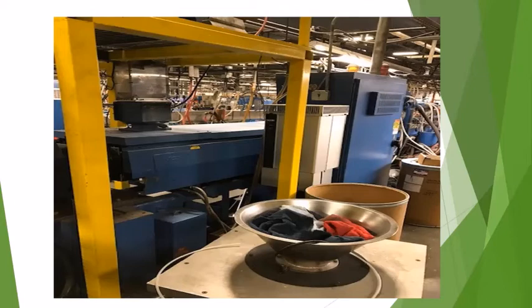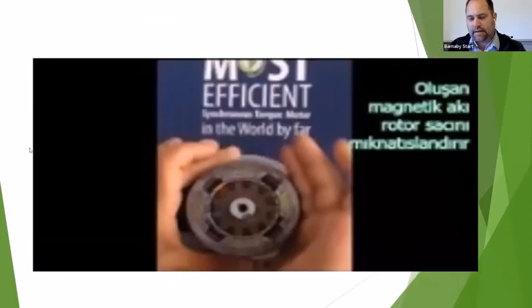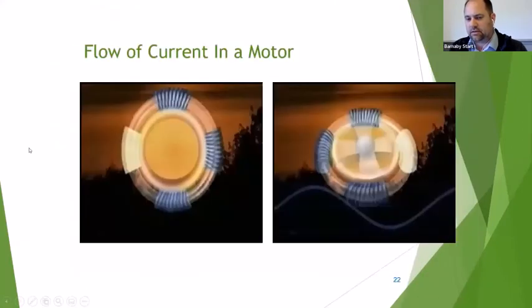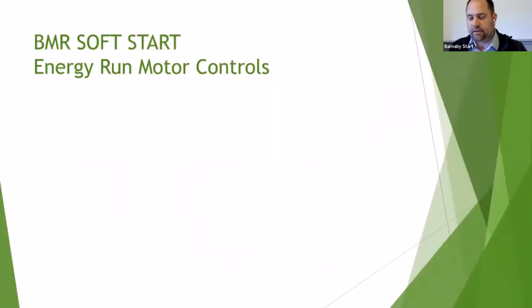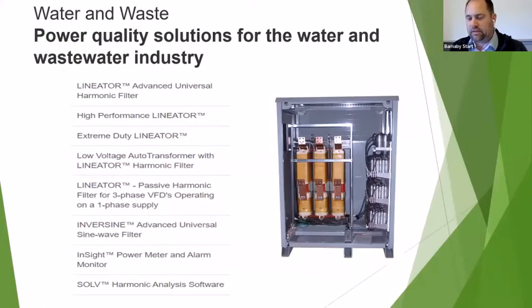Oh, there was a question here. It says, how can we reduce those harmonics in power? And maybe you want to take a stab at that, Bernie, or what we do? Yeah, I mean, like you say, you can get passive filters. If you've got harmonic problems, get passive filters or active filters that can sit behind the drive, basically between, or right next to, the drive and the supply, and that will filter out those harmonics, fifth and seventh mainly, which give you the main problems. Those are the way to get rid of the harmonics with the supply.